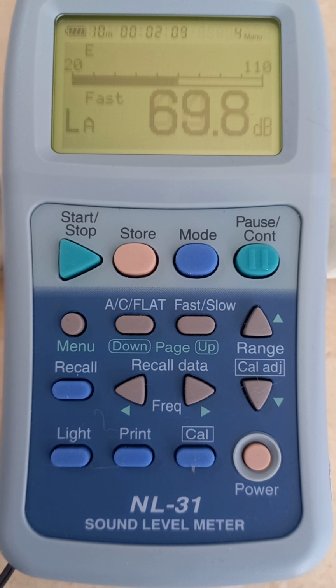They'll also do a measurement for, say, 10 minutes as well, where we measure the ambient noise level without the generator or noise source, the noise complaint source, being running. You need to switch that off, and then you need to measure for a 10-minute period in something called L90, which is your percentile, 90 percentile, and it gives you a background noise level.